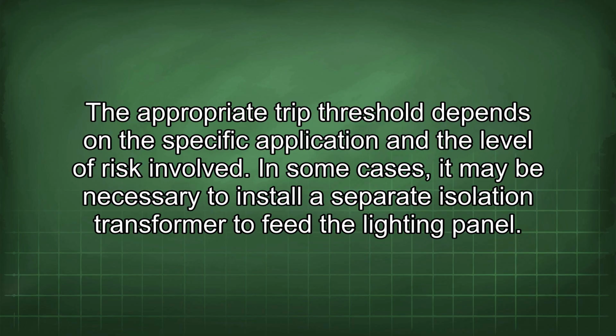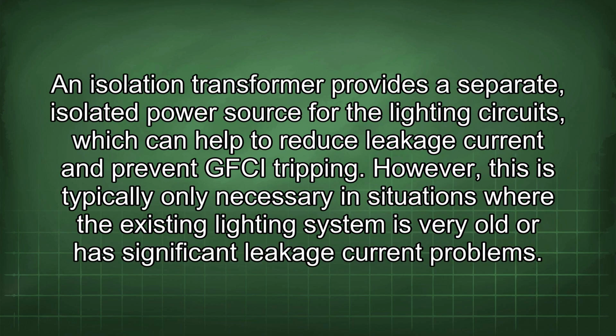In some cases, it may be necessary to install a separate isolation transformer to feed the lighting panel. An isolation transformer provides a separate, isolated power source for the lighting circuits, which can help to reduce leakage current and prevent GFCI tripping. However, this is typically only necessary in situations where the existing lighting system is very old or has significant leakage current problems.